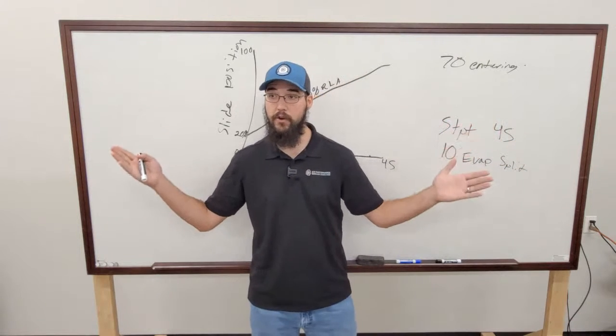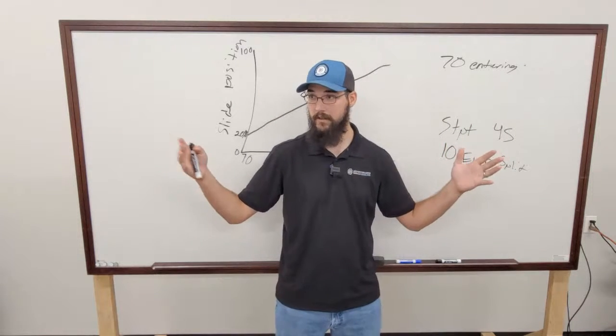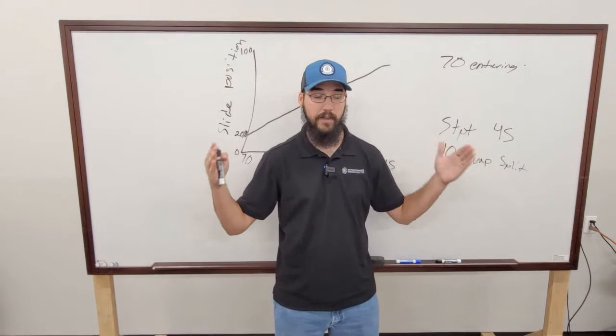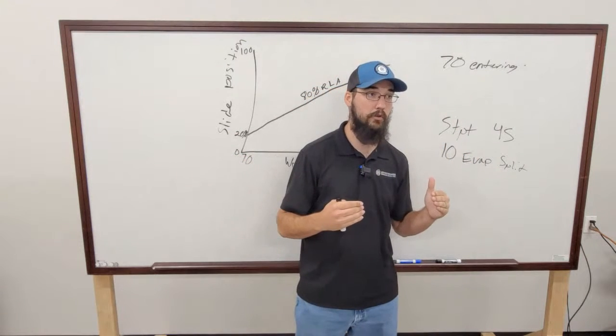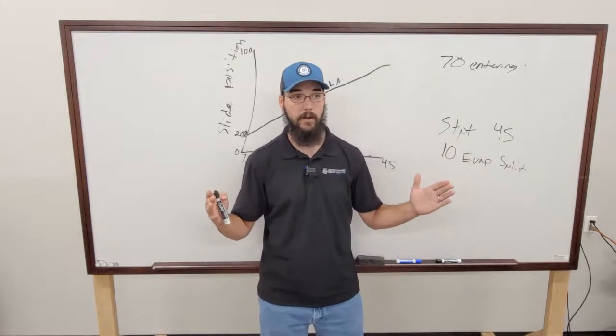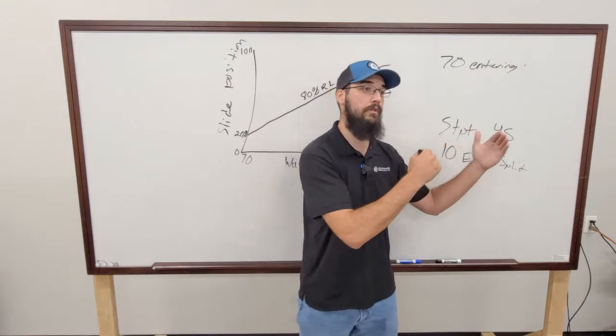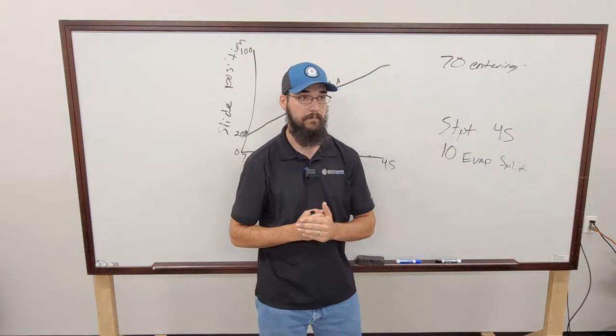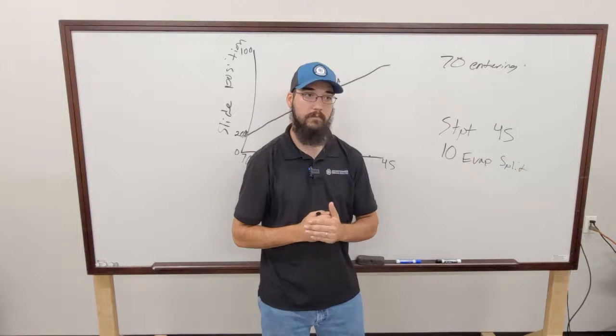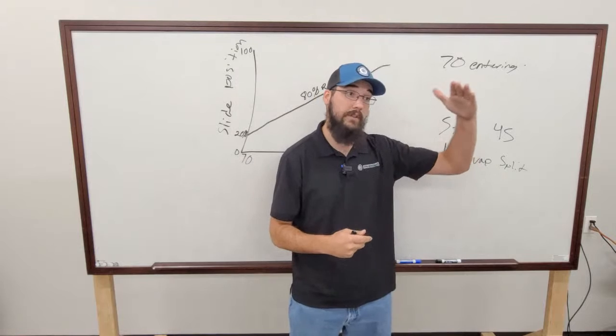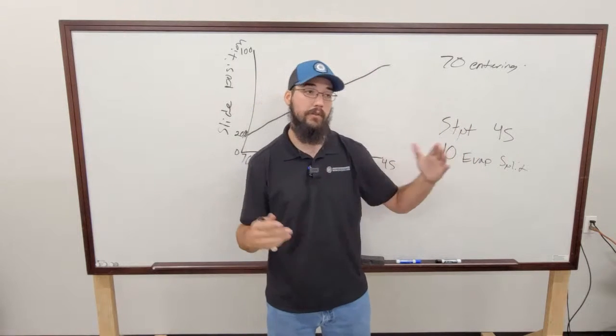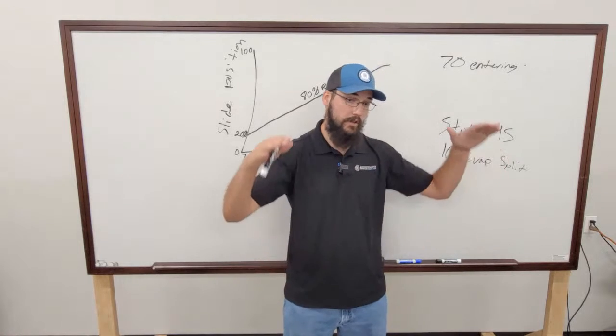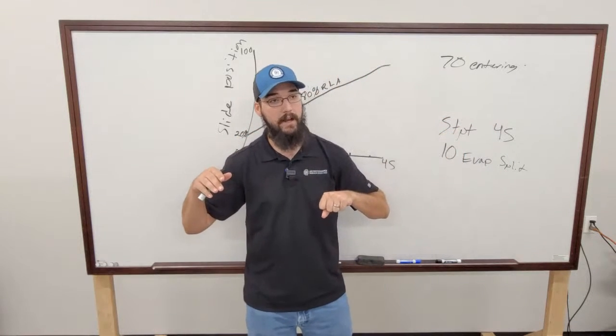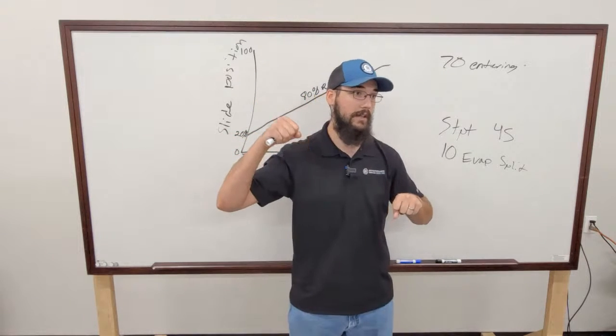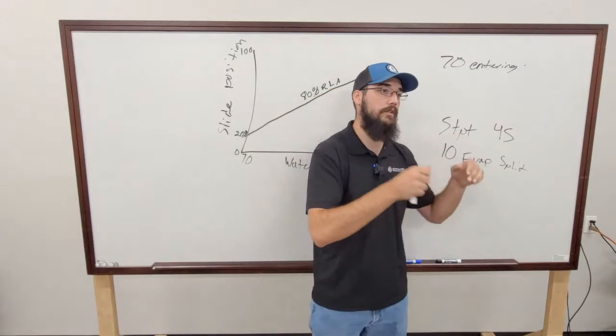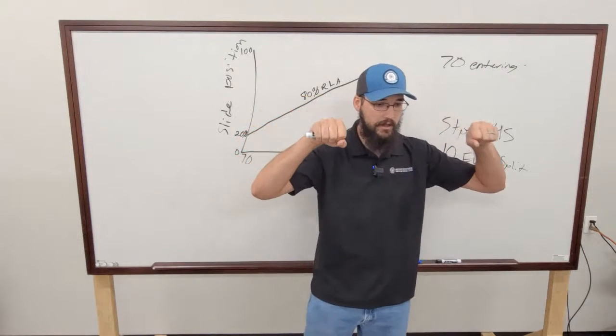A lot of times they'll have like a 30-minute delay, to where if that chiller cannot process that loop down to set point within a 30-minute time frame, they will enable the lag chiller and let them both run together to process that load down all the way to set point. And once it holds set point or lower for 30 minutes, and the chillers can start to stage down, then it will drop that lag back out and just run the primary or the lead.